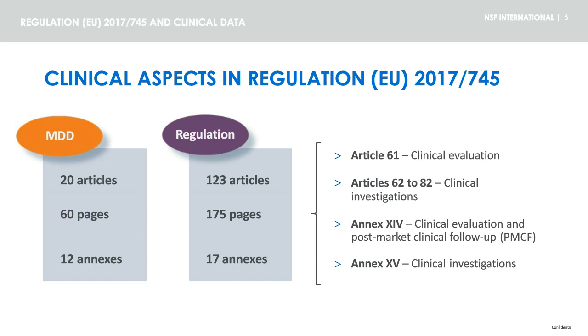Article 61, which covers clinical evaluation, Articles 62 to 82, and Annex 15, which address clinical investigations, and Annex 14, which focuses on clinical evaluation and post-market clinical follow-up. Today, we will concentrate on Article 61 and Annex 14. But if you plan a study for your device, I invite you to have a look at the requirements for clinical investigations as well.